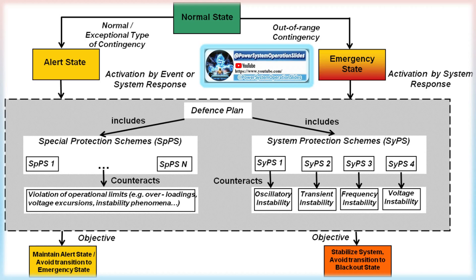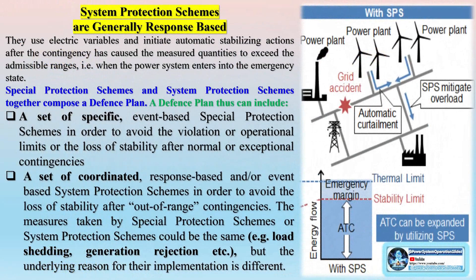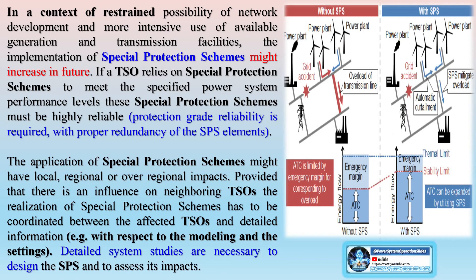Special protection schemes are often event-based and counteract a limited number of critical contingencies identified beforehand, e.g., through offline studies. Event-based means the special protection scheme is designed for operation only upon recognition of a particular combination of events, based on direct detection of the event, e.g., loss of a line. It anticipates unacceptable system conditions resulting from normal or exceptional contingencies and aims to stabilize the system in the alert state by means of dedicated automatic controls. Selected system quantities can also be monitored to trigger the scheme response-based; the power system is not necessarily in an emergency state, though there might be a risk of entering it.